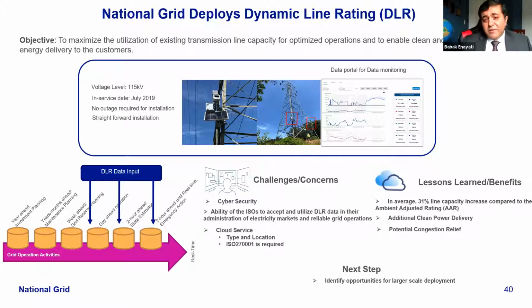On average, about 31% increase in line capacity compared to ambient adjusted rating. There's a lot of discussion in the industry around the FERC NOPR on AAR adoption and mechanisms to adopt ambient adjusted rating. However, our data shows that going beyond that and implementing dynamic line rating gives an additional 31% capacity, which is huge, opening up more room for clean energy delivery.